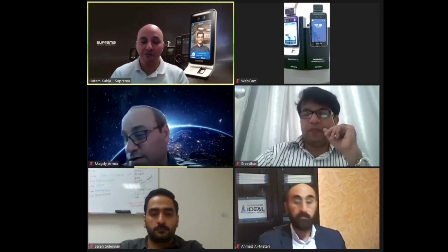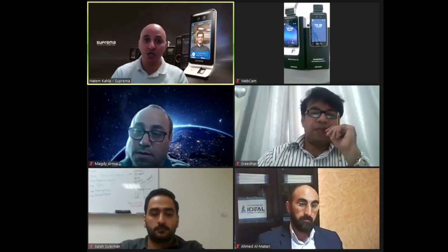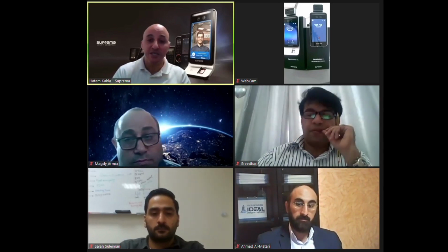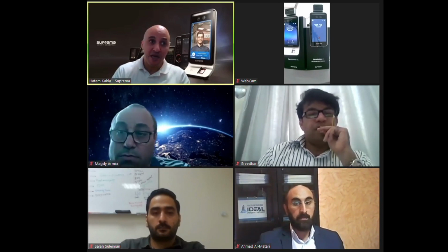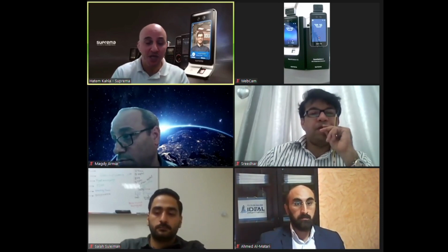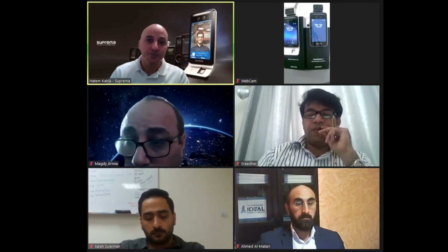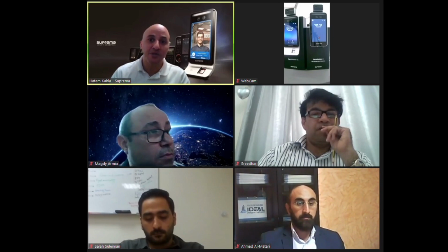Let me talk on behalf of our Middle East region. Usually I'm having this argument and debate with the consultants when it comes to this particular point, which Engineer Magdi has just raised, that PoE or redundancy power. Our device, currently the FaceStation F2, does not have PoE and cannot support PoE in the future. However, if the power is critical, then the power source for the adapter, which is 24-volt DC to power up the device, this power source, 13 amp to 230 volt, or whatever in other regions, maybe it's 110 volt, should come from emergency generators or a UPS, to make sure that there will be a backup of certain time to keep the device alive as per the battery or as per the design.